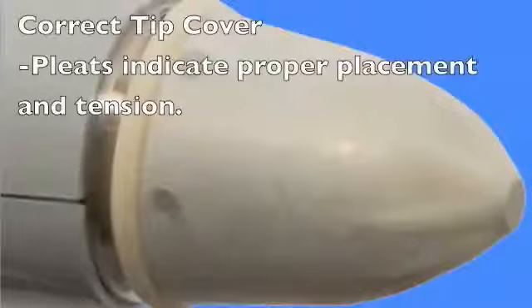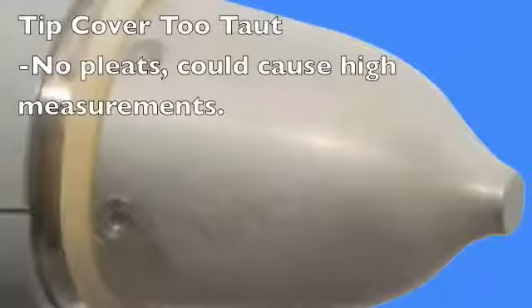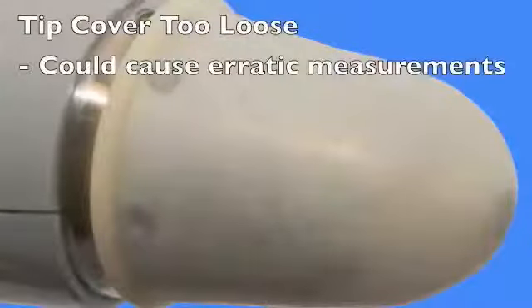This photo is an example of a properly placed tip cover. Pleats indicate proper tension while allowing the transducer pin to move freely. Tip covers that are too tight could introduce false resistance to the transducer pin and IOP measurements could read higher. Tip covers that are too loose can fold over or crease and possibly create erratic measurements with your AccuPen tonometer.